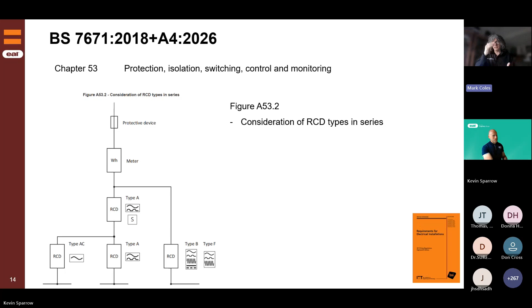To an extent, yes. For instance, when you buy washing machines, dryers, dishwashers, there's a certain type of high-end manufacturer that requires a Type F RCD. Type F are very expensive, but that's what's happening - the equipment's putting out these kind of DC currents, affecting the RCD. So this is a good, helpful image to allow you to decide which type of RCD you're using and where it goes in the installation in terms of upstream, downstream of all this.